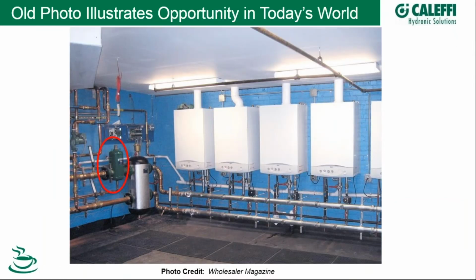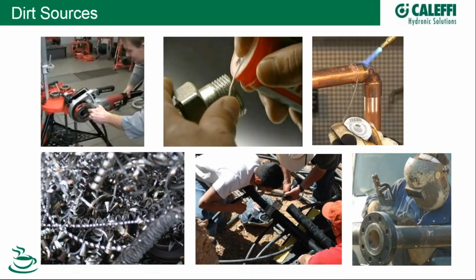So jumping to the functionality added in today's hydraulic separators, here's a photo that would depict opportunity in today's world. It's a Caleffi hydraulic separator, creating separation of all these five or six primary circulators from these Baxi condensing boilers, nicely sized headers, by the way. And along the left-hand side, you can't see, but there are several zones, mini circulators driving up to deliver heat into the building. So the hydraulic separator has decoupled all of those, but the designer wanted dedicated coalescing air separation, so he added a second component, a Caleffi Discal air separator. He would not have to do that in today's world with functionality built into the hydraulic separator.